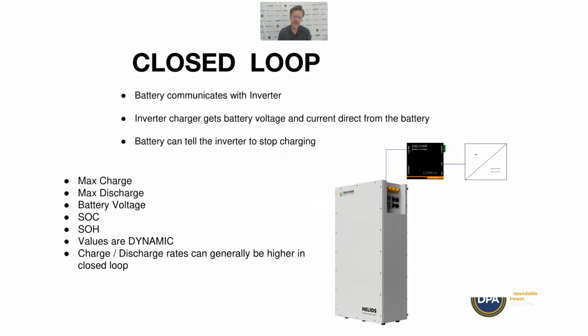So for closed loop communications, the battery is talking to the inverter, and it's basically sending it information about the battery, and it's sending it a target voltage and a target current. It's also sending it the state of charge, the terminal voltage, the state of health, but its main job is to send that target voltage and that target current, charge current and discharge current, so it can effectively tell it when to turn off its charging or its discharging.